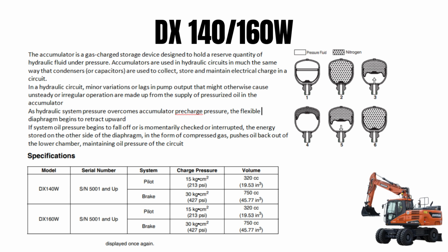Minor variations or lags in pump output that might otherwise cause instability, irregular operation, are made up from the supply of pressure oil in the accumulator. So if there is unsteady or irregular flow from the pump, this makes it balanced and stable. This absorbs the pulsation from the hydraulic flow. When hydraulic system pressure overcomes accumulator pre-charge pressure, the flexible diaphragm begins to retract upward, as I already told. If system oil pressure begins to fall off or is momentarily checked or interrupted, the energy stored on the other side of the diaphragm in the form of compressed gas pushes oil back out of the lower chamber, maintaining oil pressure of the circuit.